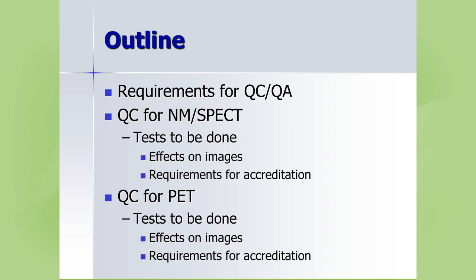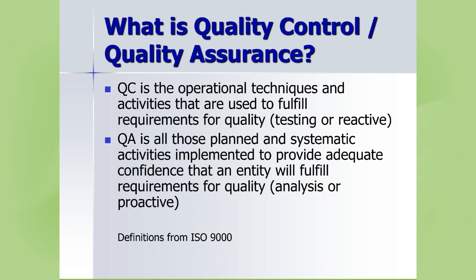Per ISO 9000, quality control and quality assurance are slightly different. Quality control is the operational techniques and activities used to fulfill requirements for quality — this is testing you do reactively when something may be causing an issue in your images. Quality assurance is a planned, systematic activity to provide adequate confidence that things are working properly — it's analytical and proactive, done before you notice a problem so it isn't impacting clinical work.